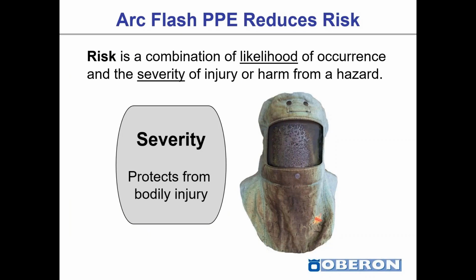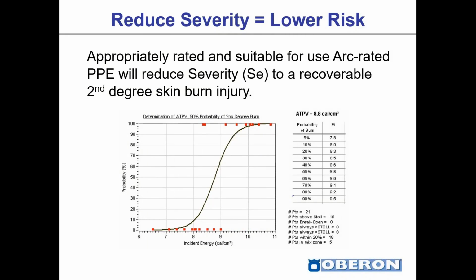The arc flash PPE is designed to reduce risk. It actually reduces the severity of the bodily harm. So the injury to the worker is reduced by using arc flash PPE. And again, risk is a combination of likelihood of occurrence and the severity of injury or harm from a hazard. The PPE then protects from the bodily injury. We reduce the severity by lowering the risk, so appropriately rated and suitable for use arc-rated PPE reduces the severity to a recoverable second-degree skin burn injury. And here I'm referencing again that ATPV, or the arc rating that we measure and determine based on the high current laboratory and the testing that we've done.